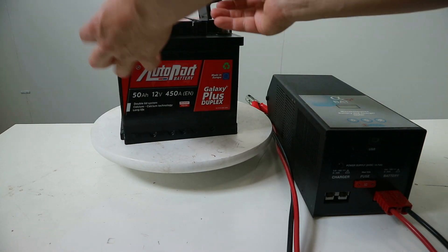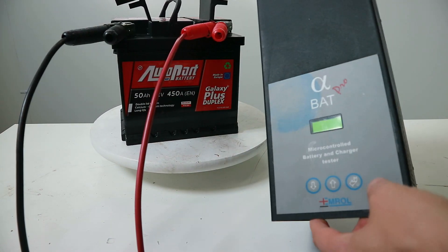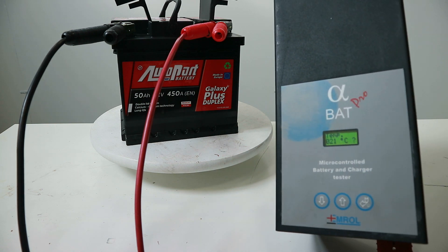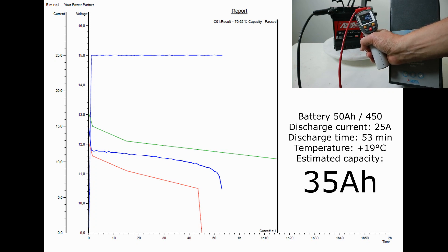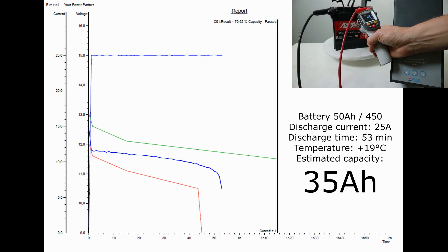Using the Alpha BAT Pro capacity tester, the battery will be discharged with a current of 25 amps until the voltage reaches 10.5 volts. Taking into account the Peukert factor and temperature, I will be able to estimate the capacity of this battery according to the C20 rating.